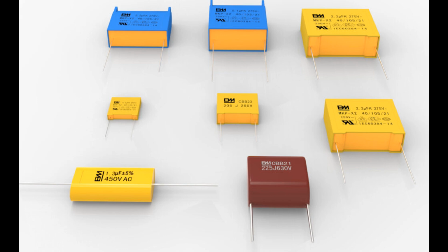2. AC motors and motor-run capacitors. AC motor-run capacitors. Film capacitors are used in AC motors, particularly in single-phase induction motors, to provide continuous phase shift and improve torque efficiency. These capacitors help maintain a stable voltage supply to the motor windings. Starting and running applications. Film capacitors are used in both the starting and running phases of motors to increase efficiency and reduce energy consumption.